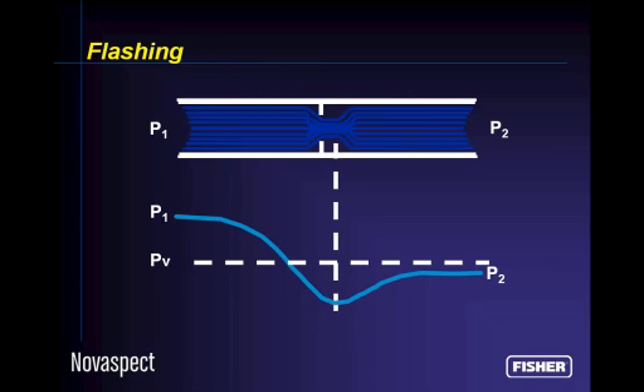Hey, there's something really different in this picture than any of the pictures I showed you. Take a second, look at that. You're going to see that the downstream pressure of the valve in this example is not above the vapor pressure, it's below the vapor pressure. Well, what the heck is going on here? What is this application called? This is called flashing, as you can see by the top of the slide. In this particular case, we come in as a liquid, we're above the vapor pressure, we drop below the vapor pressure, the liquid turns to vapor, it recovers to the downstream pressure, and it never turns back to a liquid because it's below the vapor pressure. This is a little different, a little easier to handle.